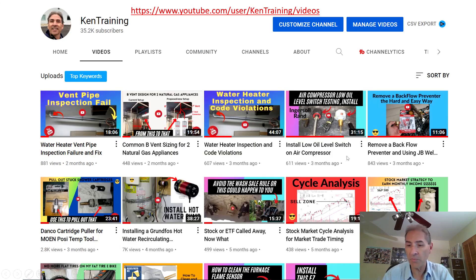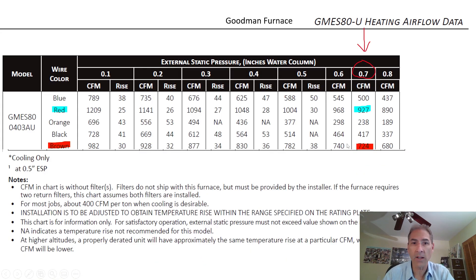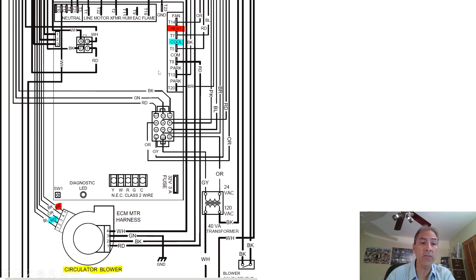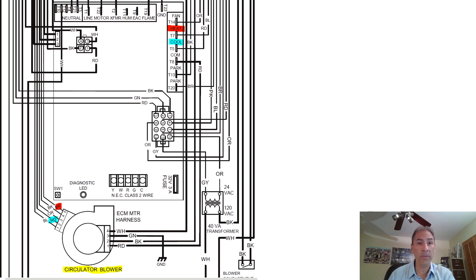You want to know your external static pressure and your CFM so that you know exactly which tap to use. This ensures you set the correct motor speed to achieve the airflow your system needs — whether in a home, a business, or any other application. It's all a system.